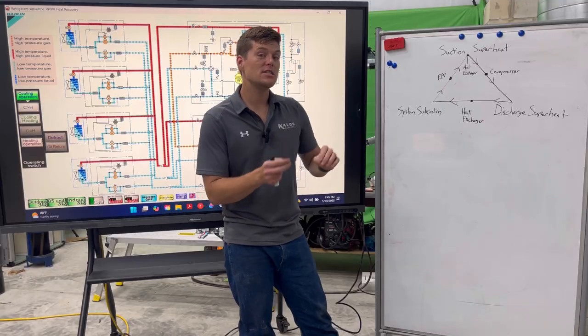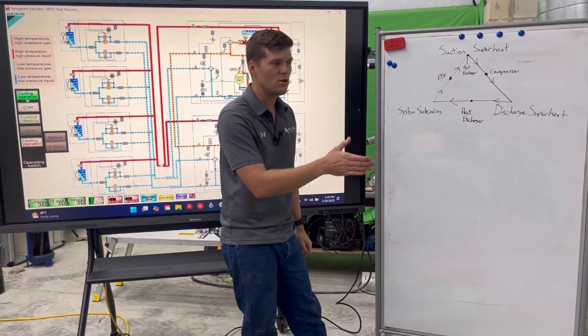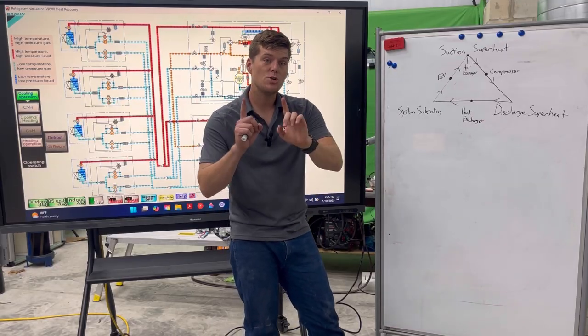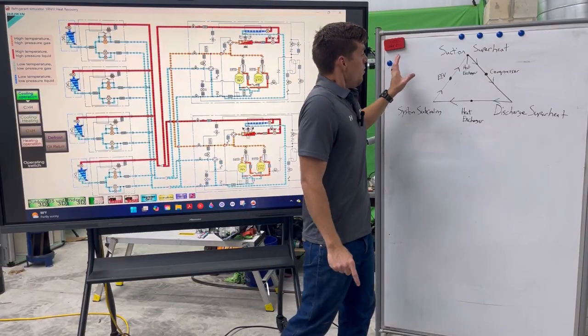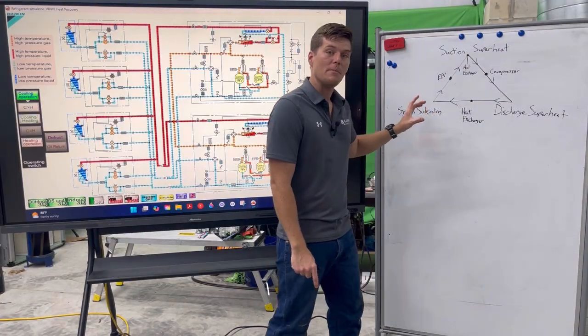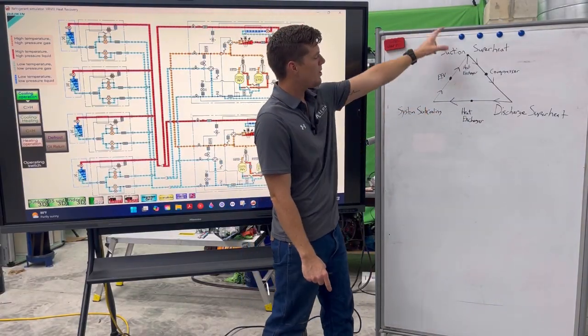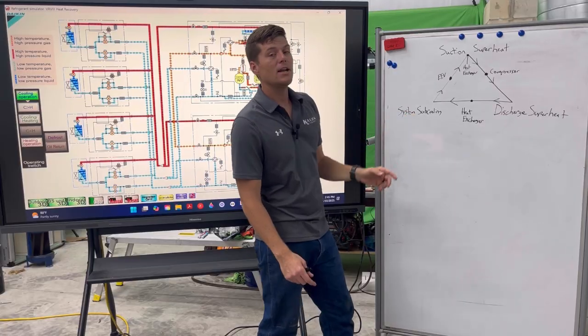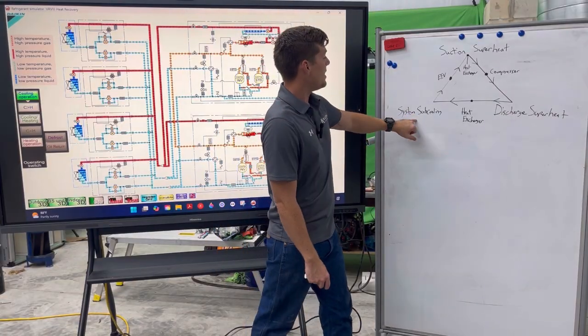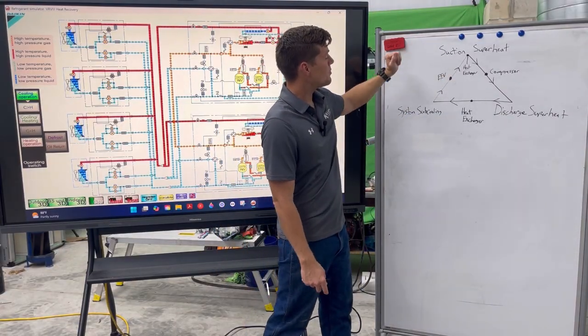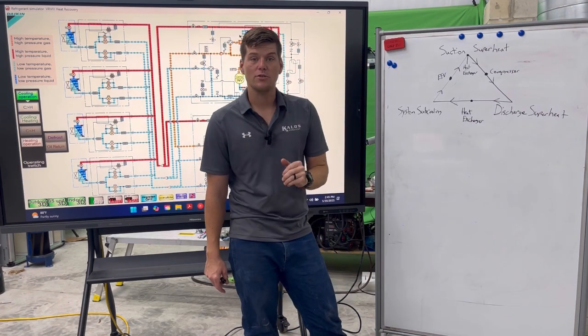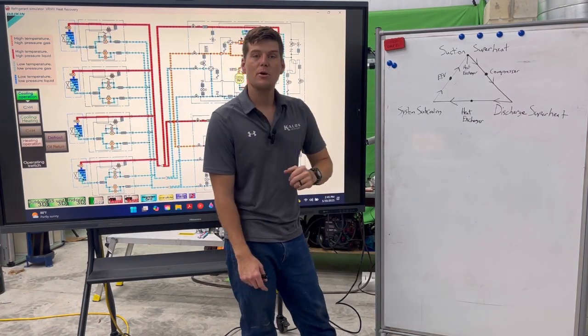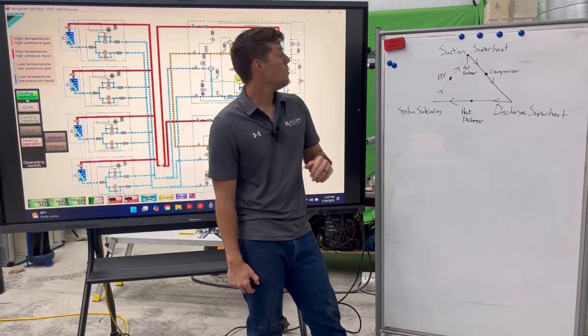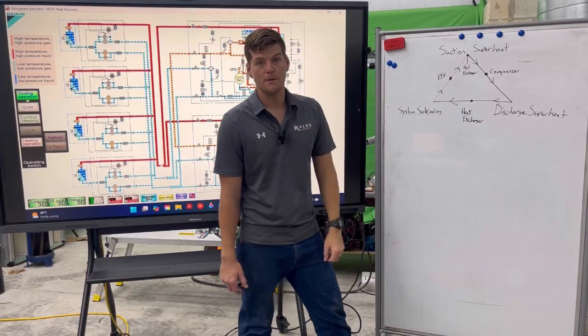And again, it's not just these numbers that pinpoint an exact location of where the problem is, but it lets you understand what the system looks like over time. Also, once I plot these numbers in these 3 corners, it allows me to understand, hey, between here and here, maybe there's a restriction. What is the expansion valve doing? Well, it's at 2,000 pulses, but there's no temperature change across it. Well, then my issue is between these 2 numbers here.